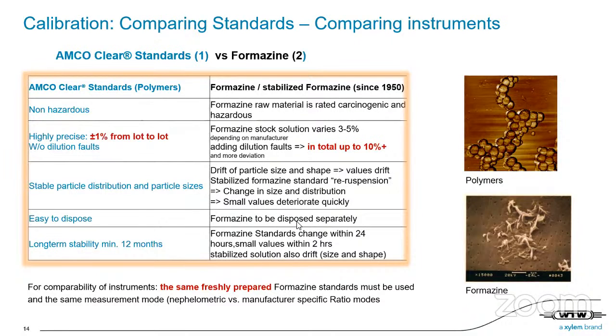We had people in our service lab complaining, also comparing instruments from other companies, saying, oh, we have done the calibration and we have done the measurement and we used a commercial stabilized formazin standard of 5 NTU and it's not matching. And then we measured it with a freshly calibrated instrument with formazin and with AMCO Clear standards, which are the most modern standards. And we found that the stabilized formazin was drifting from 5 to 3.5 or something.